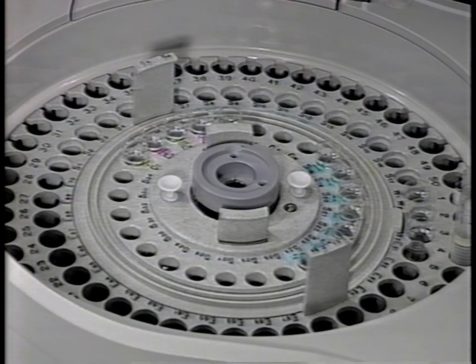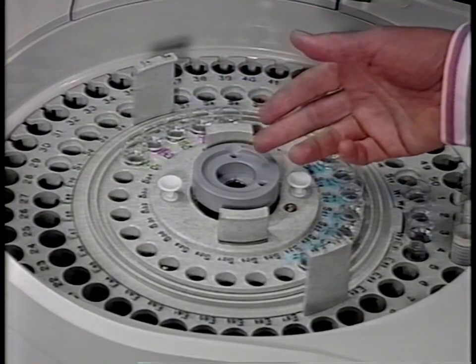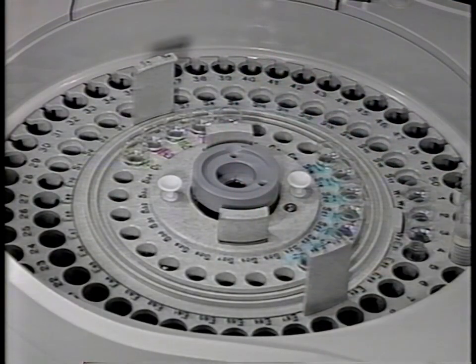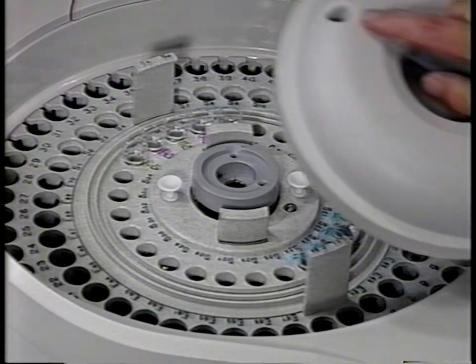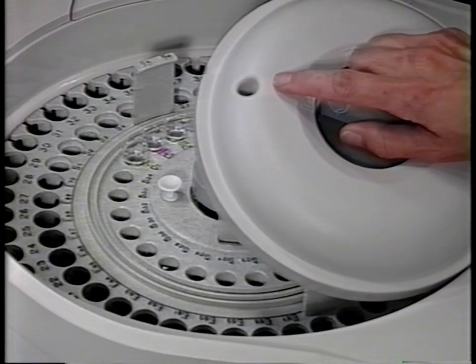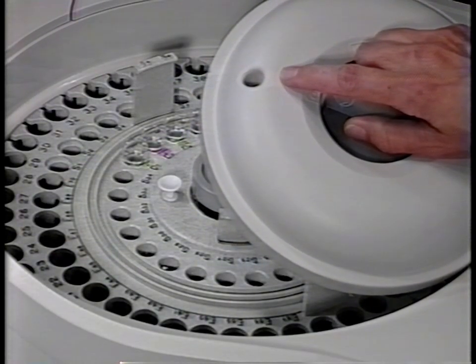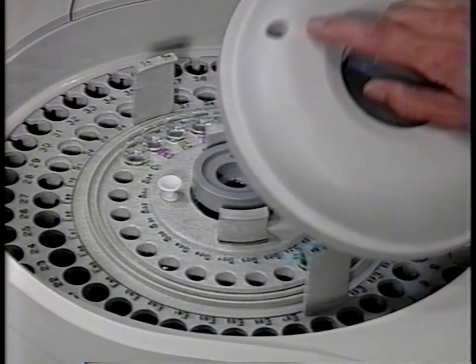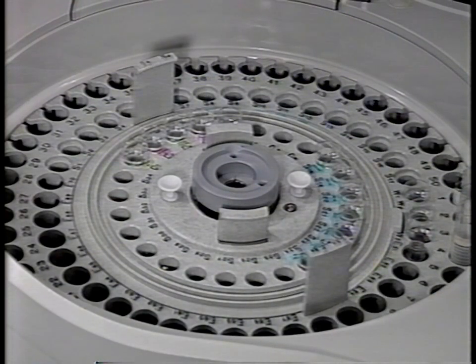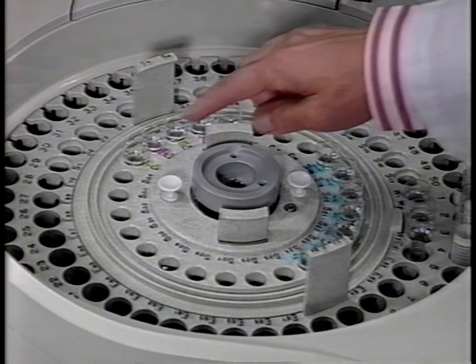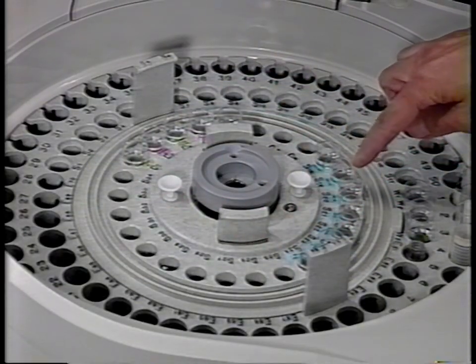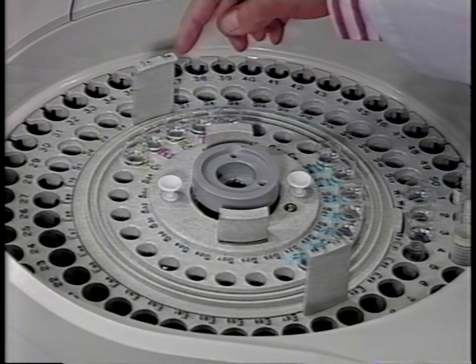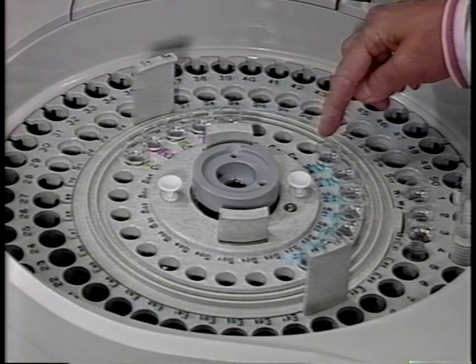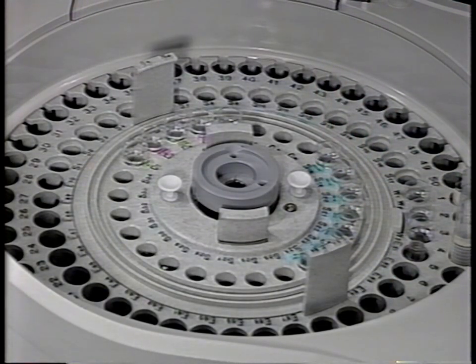The inner ring of the sample disk is located under the insulated cover. Calibrators, standards, and controls are stored here at a refrigerated temperature of 2 to 12 degrees Celsius. There's a narrow opening in the cover for the sample probe to reach the material inside. This refrigerated inner ring has positions for 17 standards and calibrators. It also has 8 positions for controls. The operator generally loads the inner ring once per shift.